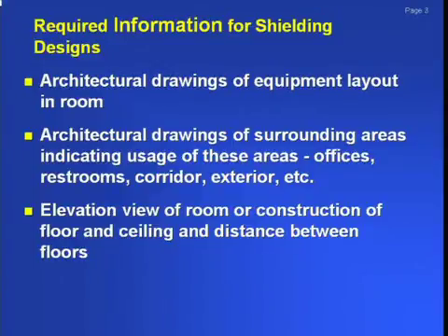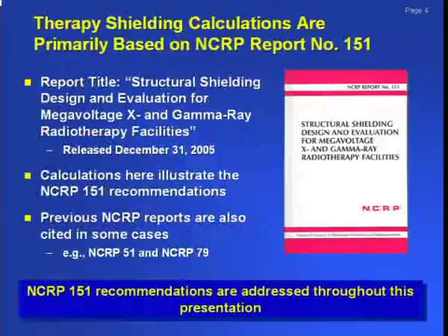So that may have been technically a separate construction project, but we had to get involved and put more shielding in that building. You need, obviously, an elevation view of the room and the construction materials, at least, of where they propose the floor and ceiling and the distance between the floors that you have to work with.